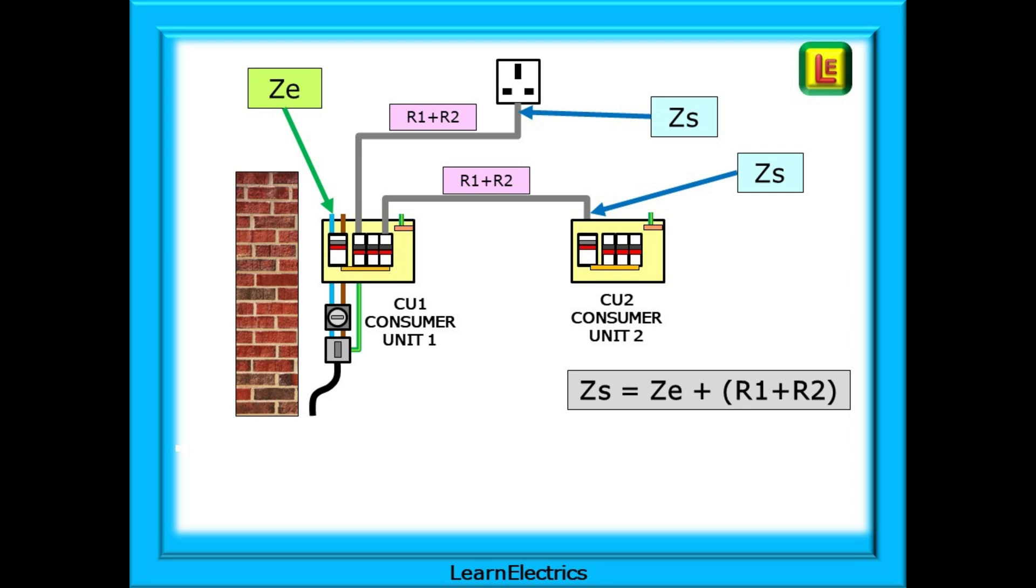At the end of each of the circuit cables we can measure or calculate a ZS. We can measure ZS at the socket for the final circuit and we can measure ZS at the main switch of CU2 for the distribution circuit. This information will be recorded on the schedule of test results in the correct row for each circuit.